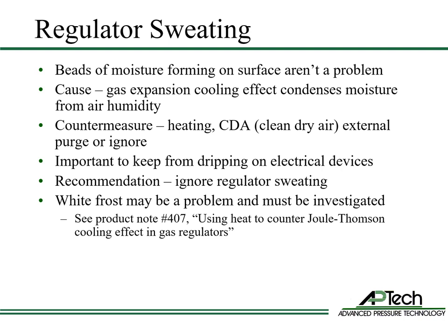The countermeasure is heating, clean dry air external purge, or to ignore. It is important to not let water drip on electrical devices. Our recommendation is to ignore regulator sweating. However, white frost may be a problem and must be investigated. See product note number 407 for more details.